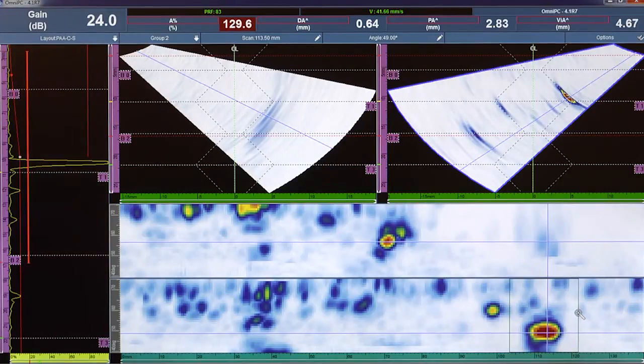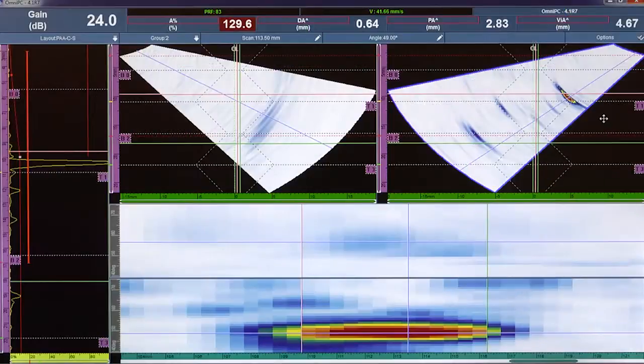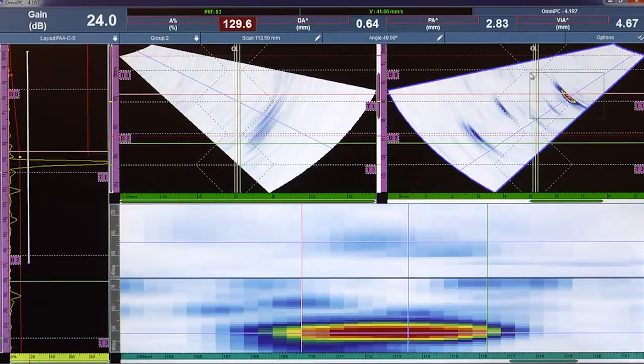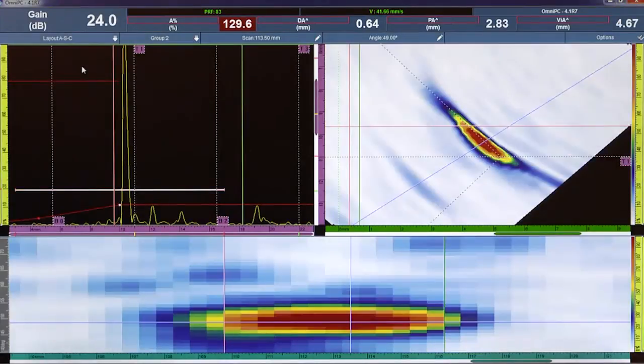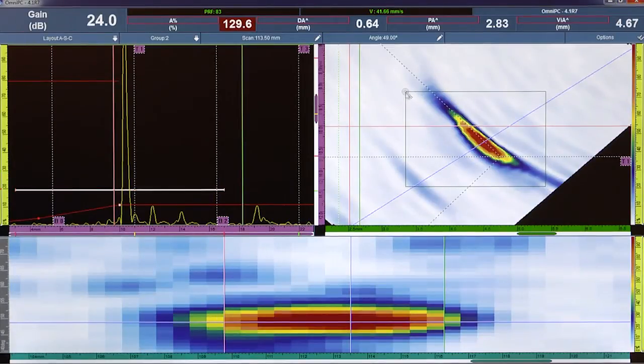When a flaw is detected, length sizing is performed with the cursor on the C-scan using an amplitude drop technique and the statistics displayed in the readings from the scan axes. Depth and height sizing is performed with cursors on the S-scan using amplitude drop or tip diffraction techniques with statistics available from the UT axes.